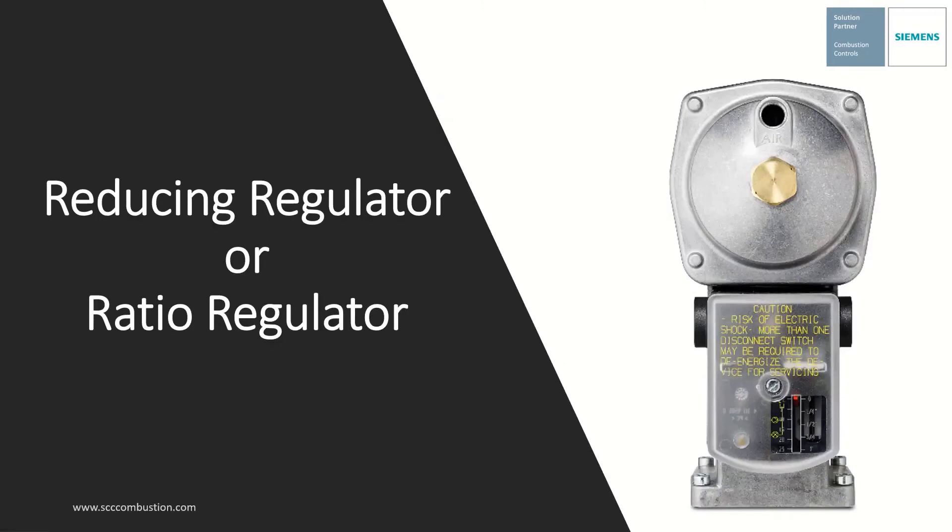The SKP25 is a reducing regulator or a ratio regulator. In the picture, you can see a round diaphragm at the top. You can see the port on the front is labeled air. This port is when being used as a ratio regulator. The gas sensing port is on the back. The brass plug is for the spring when being used as a reducing regulator or a bias spring for a ratio regulator.